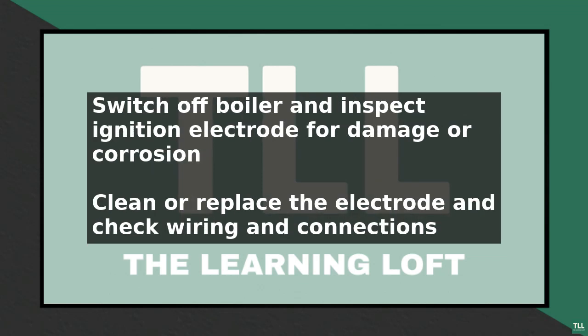Check the wiring and connections to ensure they are secure and not damaged. Verify that the electrode is properly aligned and seated. If the issue persists, it may be necessary to replace the ignition controller or consult a professional for further assistance.